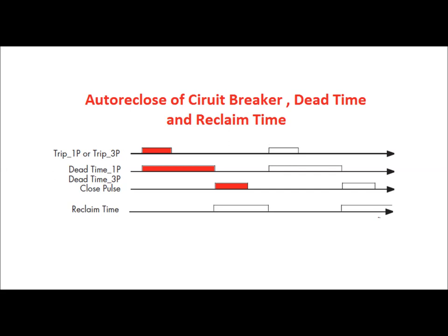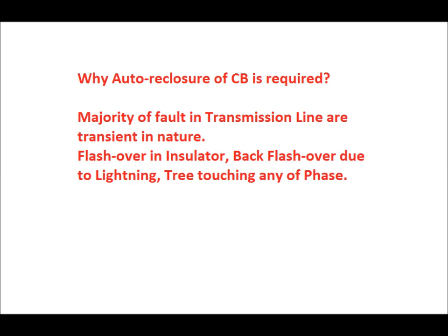Today I will discuss auto reclose of circuit breakers, dead time, and reclaim time. When a fault occurs in a transmission line, the relay senses the fault and sends a trip signal to the circuit breaker, which trips and clears the fault. After that, human intervention is required to normalize the line — the closing pulse is given by operating personnel, causing a time delay.